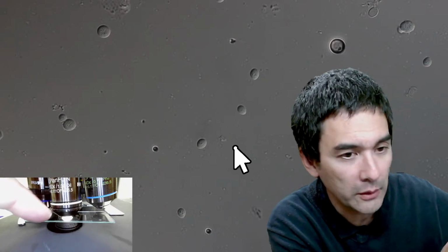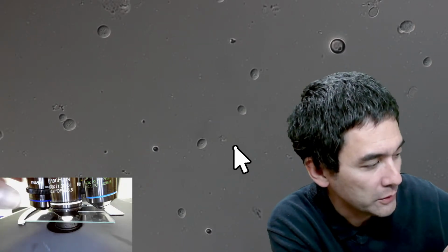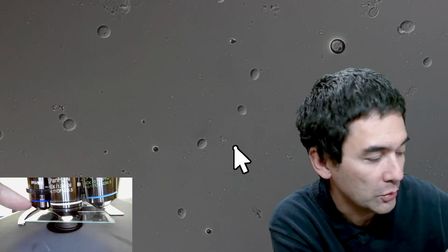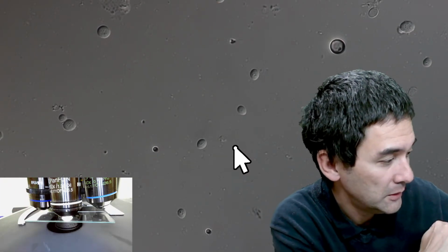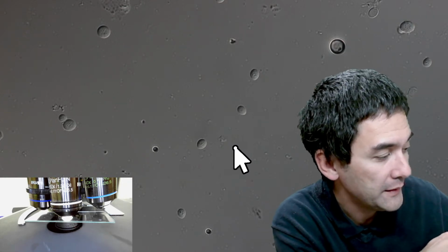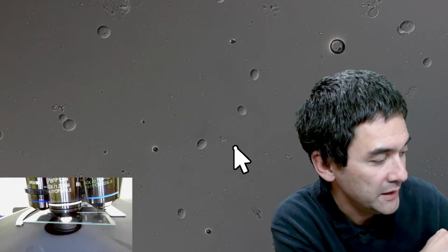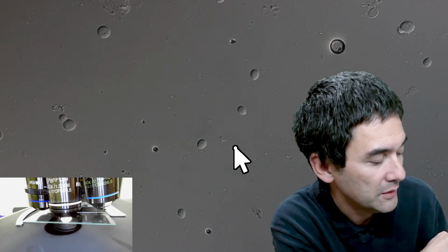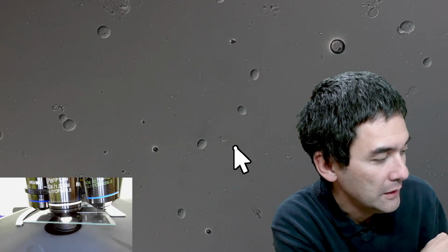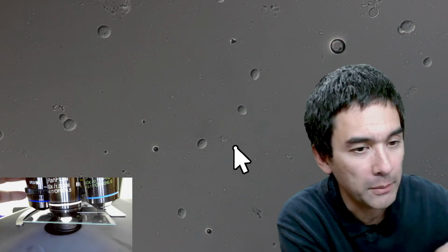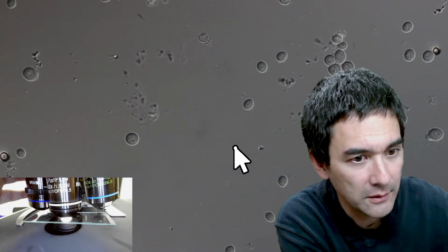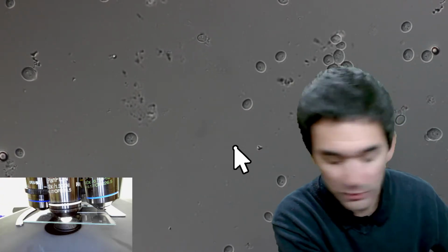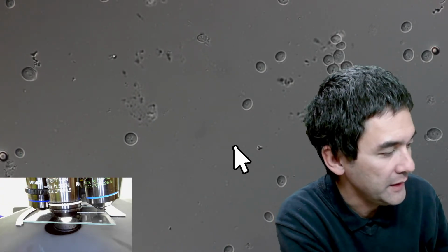Once you've got immersion oil on here, do not switch back to the lower magnification, because otherwise you're going to contaminate those as well. And be careful that you don't crash the slide into the objective. To remove the bubbles, you can go back and forth a little bit like this. But I would like to now show you how I clean the whole thing.